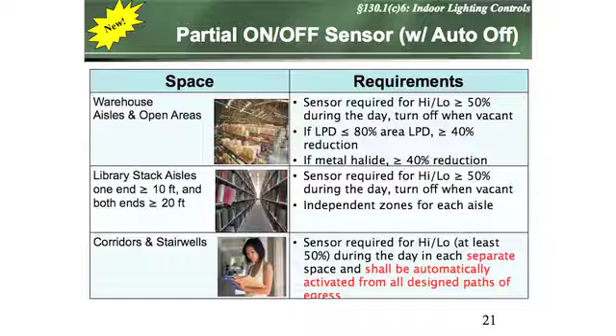So somebody could have it lit so it's always at half level, and then when they walk into the stacks, the light goes full on. And then here's where it gets kind of interesting. Corridors and stairwells: this is a requirement for that same high-low with an automatic off. So they're saying that for corridors now, you have to have an automatic off at night. Now, you can still have the egress lighting on, but this is a huge change, because before, corridors were completely exempt from the code.